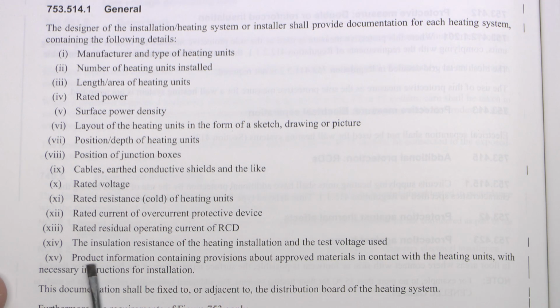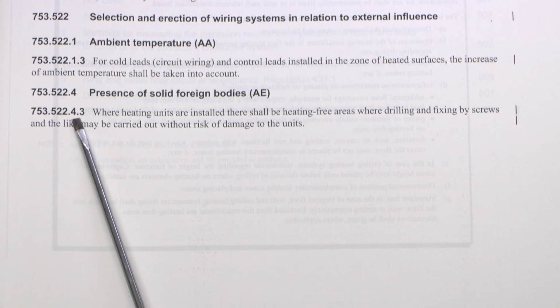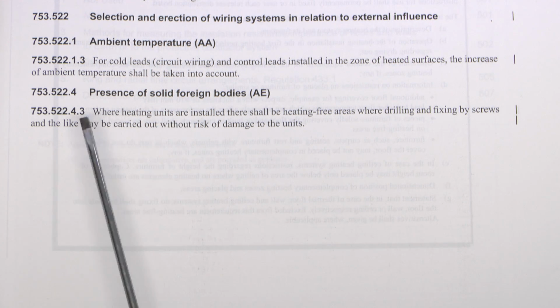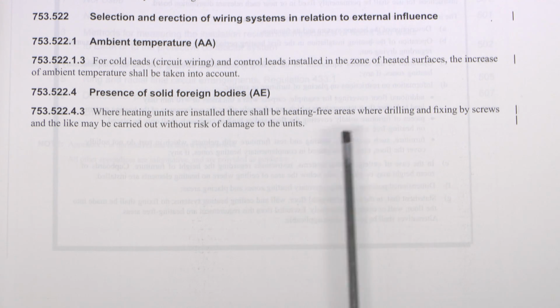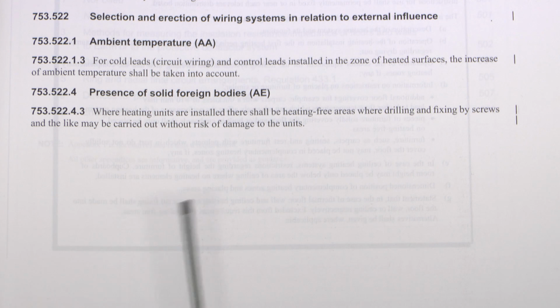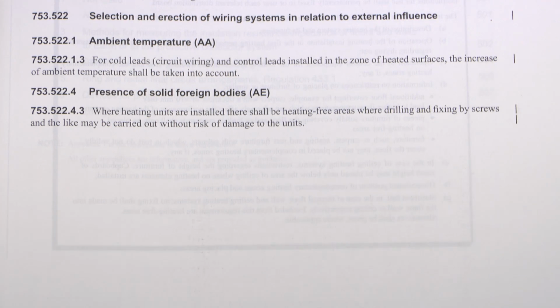And at the bottom here we've got product information containing provisions about approved materials in contact with the heating units, with necessary instructions for installation. Again, that is a new item. And also previously it referred here to a plan, and now it says documentation. 753.522.4, there was previously a section here which required that the installer shall inform other contractors. Well, that's been deleted, and we've still got the original text here about risk of drilling and screws and so on. We're obviously providing heating-free areas for such items, so you don't have to inform other contractors any longer.